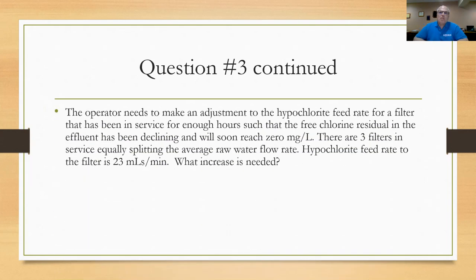So here's the question: The operator needs to make an adjustment to the hypochlorite feed rate for a filter that has been in service for enough hours such that the free chlorine residual in the effluent has been declining and will soon reach zero milligrams per liter. Now there's three filters in service, all equally splitting the average raw water flow rate. One of them has been in service a lot longer than the other. The hypochlorite feed rate to the filter is 23 milliliters per minute. What increase is needed?